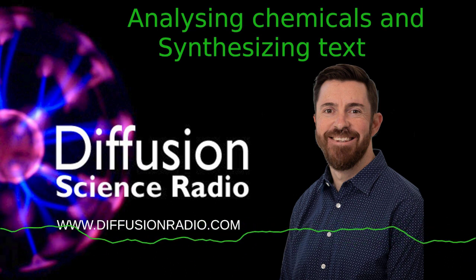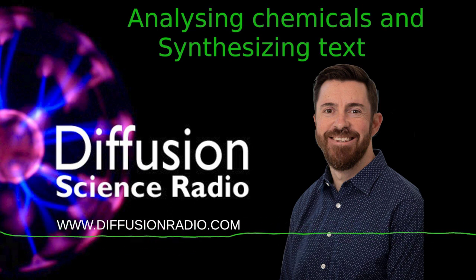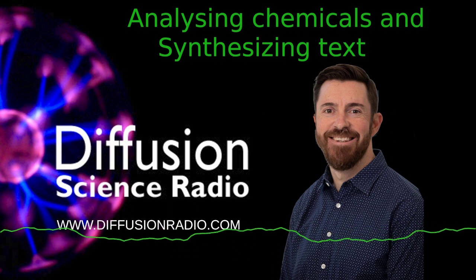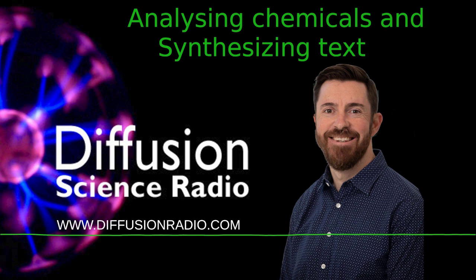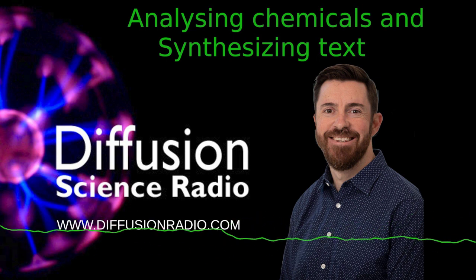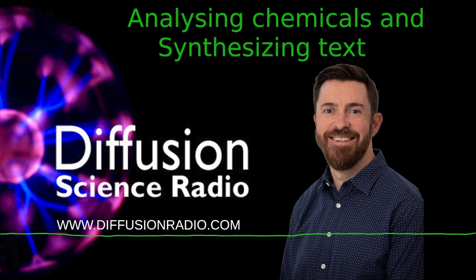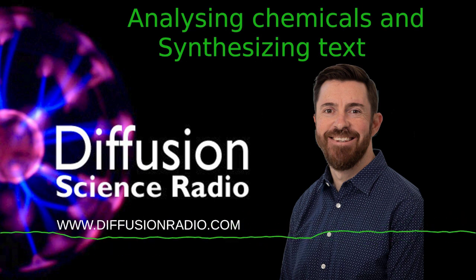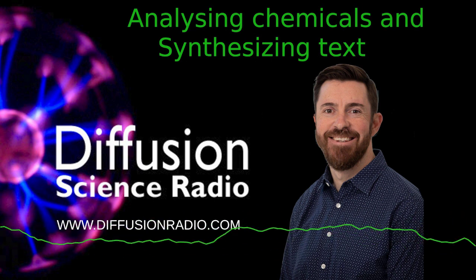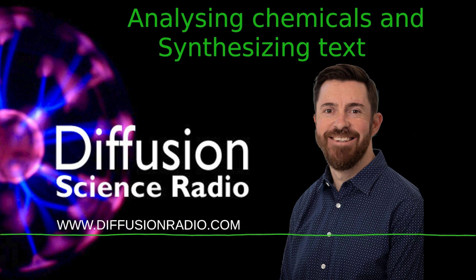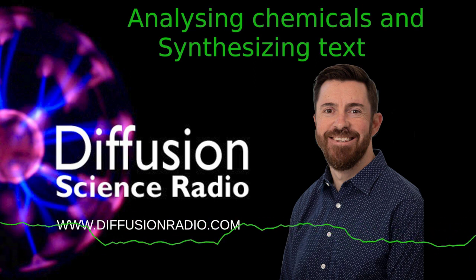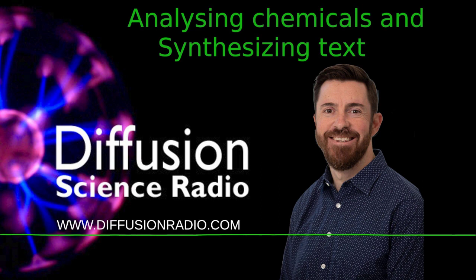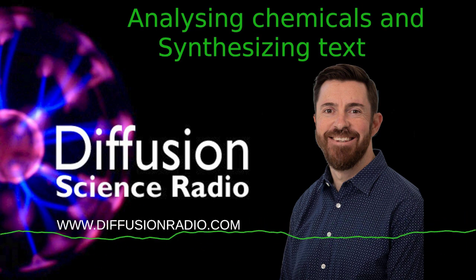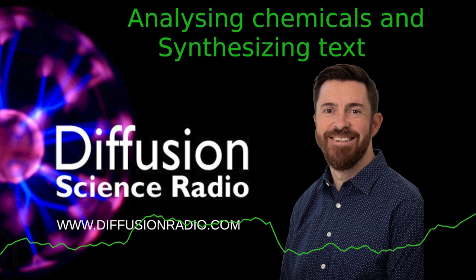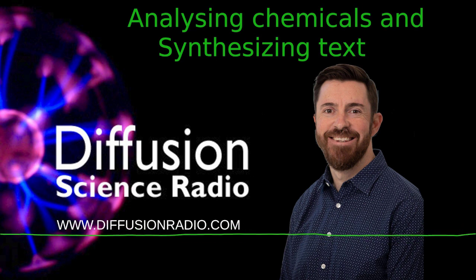So you've now got your metals or whatever it is you're trying to detect, which could be biological samples, could be all sorts of things. It's been aerosoled down to very tiny amounts and it's been heated up and electrically charged with the plasma. What happens next? It then enters the mass spectrometer. From the mass spectrometer, it is focused through into what we call a quadrupole analyzer. And here, only one ion at a time will go through to the detector.